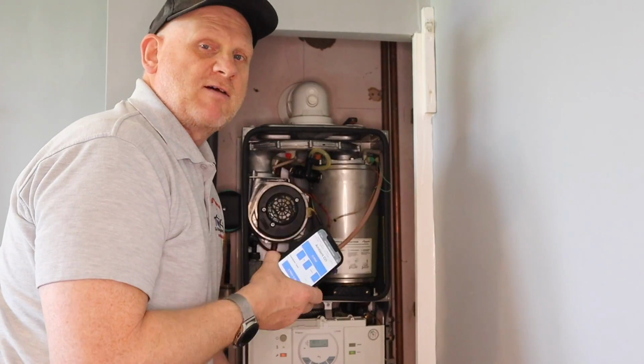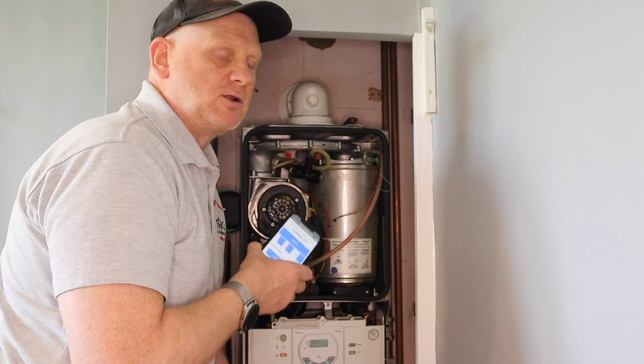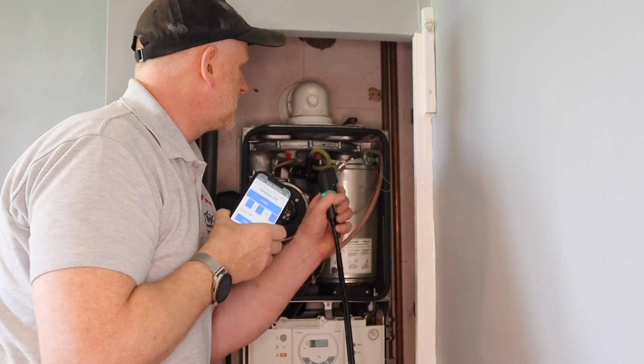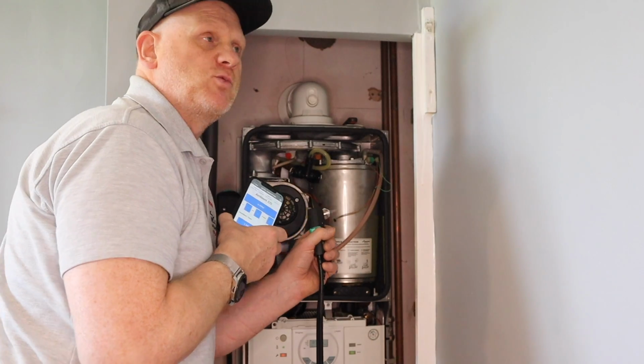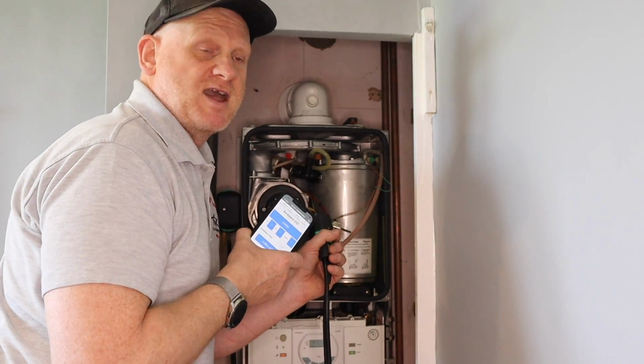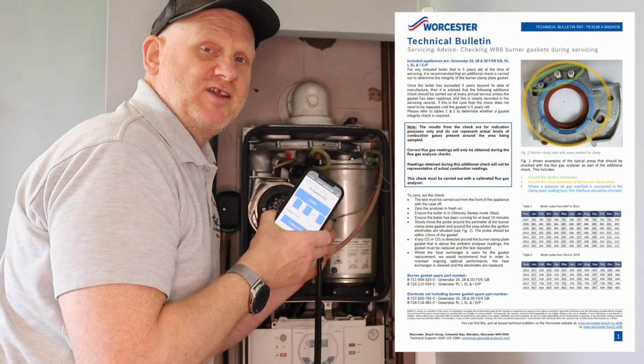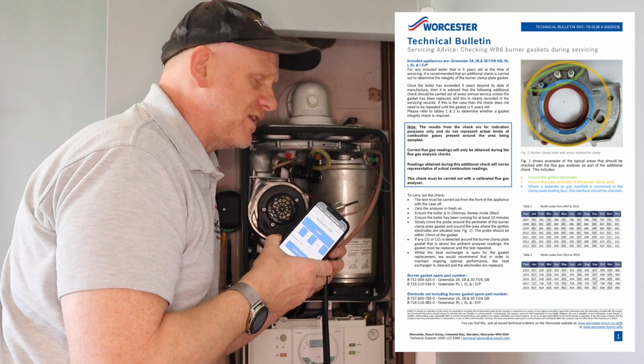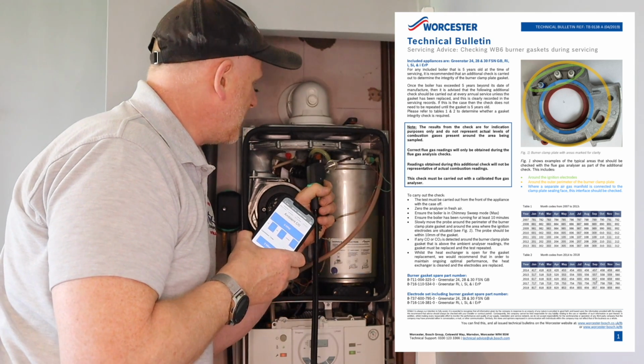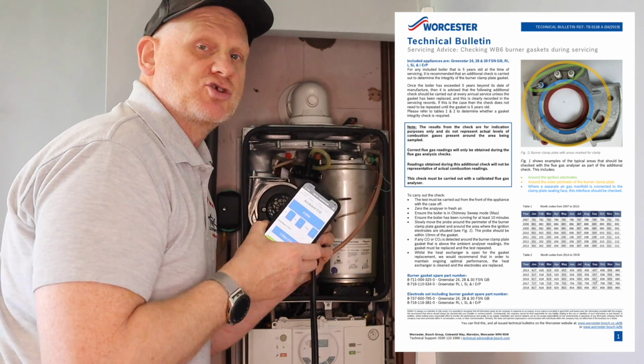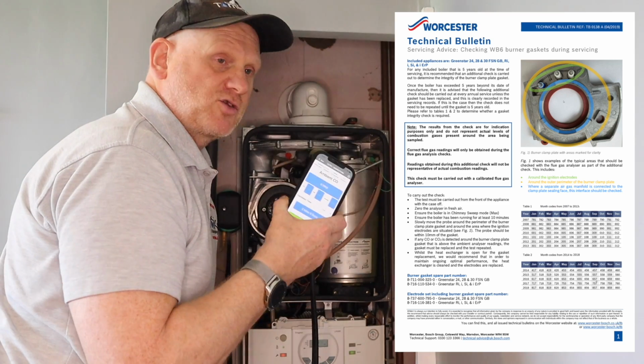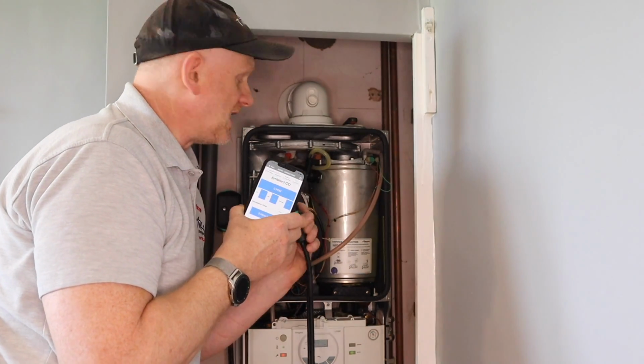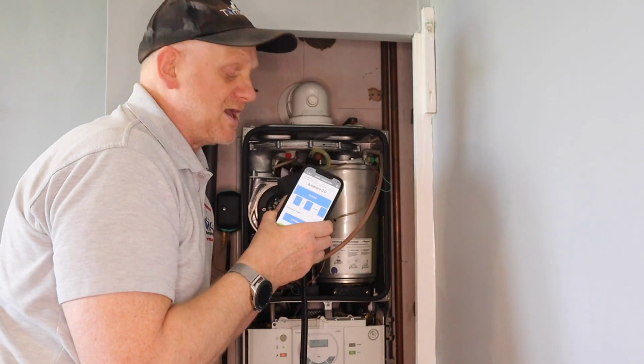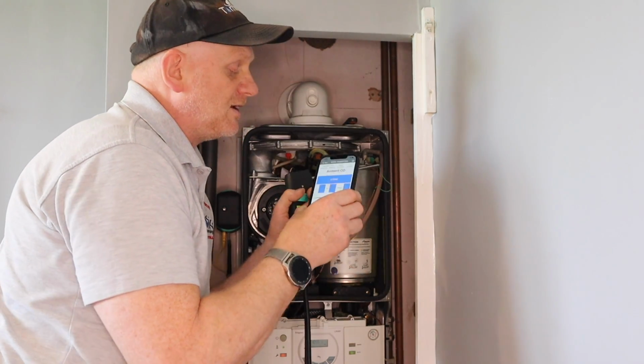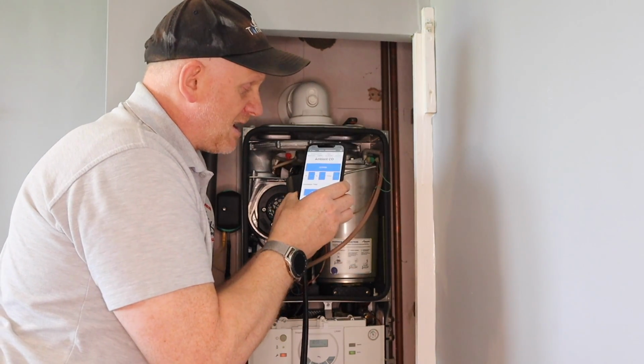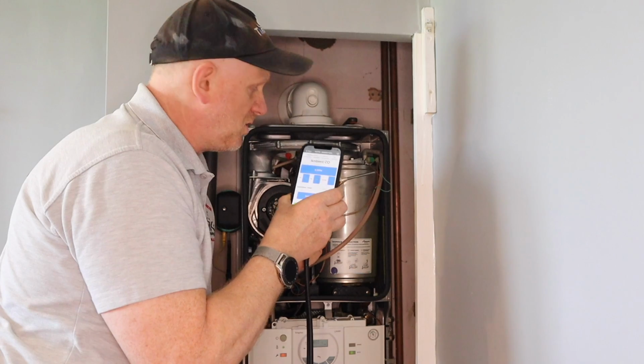So now the boiler's been running for a little while, what we've got to do, because we've changed the gasket up here, is do a sweep test. Now, Worcester have issued a technical bulletin on this, and they say when you change this gasket you must carry out a sweep test. So the sweep test is done with your flue gas analyzer. So I've got my TPI DC710 set up. I've got it on my app here, my ambient CO. I've set it for 2 minutes.